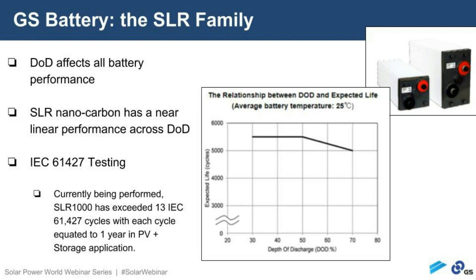It holds the battery temperature at a nominal 40 degrees C. It will take the battery through a shallow cycle charging profile: you recharge the battery, discharge 3 hours, recharge 49 times. Then a second phase is high state of charge cycling, where you discharge to a much higher state of charge 100 times. That's supposed to simulate one year of performance in a PV energy storage application.